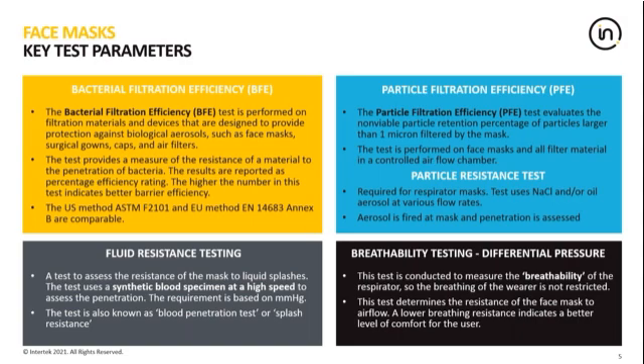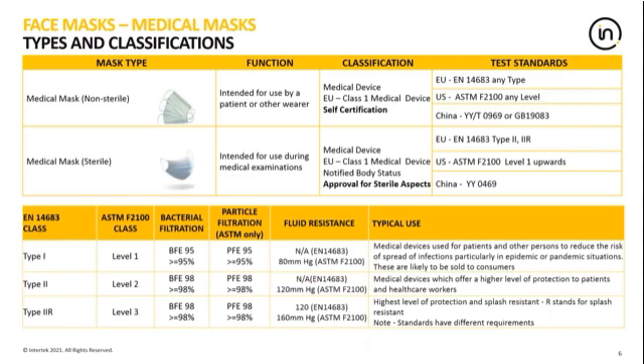This means that the breathability test, or differential pressure testing, is key. This is a test which assesses how easy it is for a wearer to breathe comfortably. And the test determines the resistance of the face mask to airflow. A lower breathing resistance indicates a better level of comfort for the user. If you recall, medical masks can be classified into two categories: non-sterile and sterile. The non-sterile mask is intended to be used by a patient or other user to prevent transmission, and these are defined as medical devices.